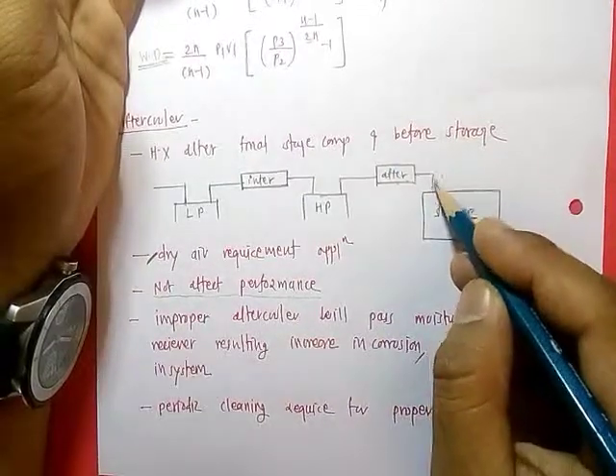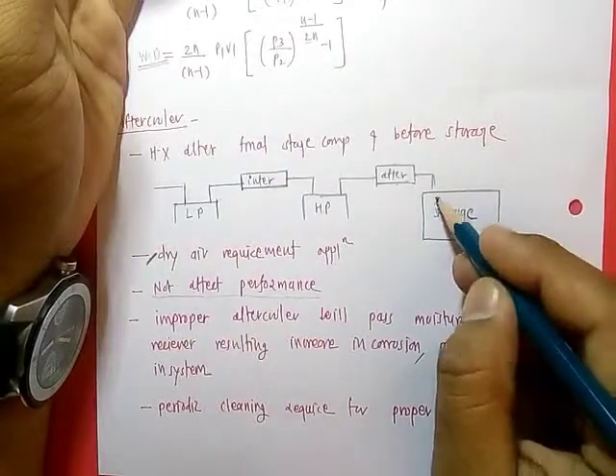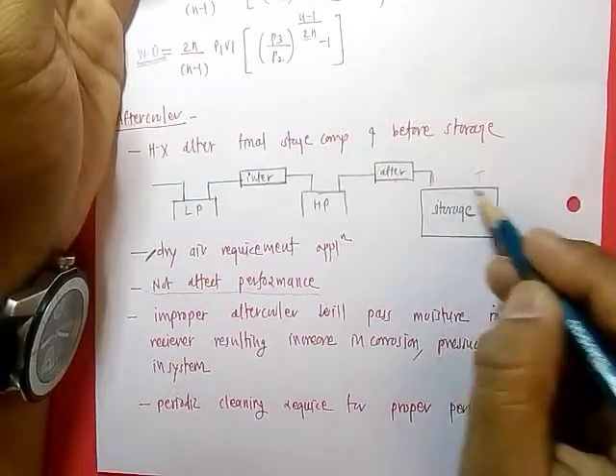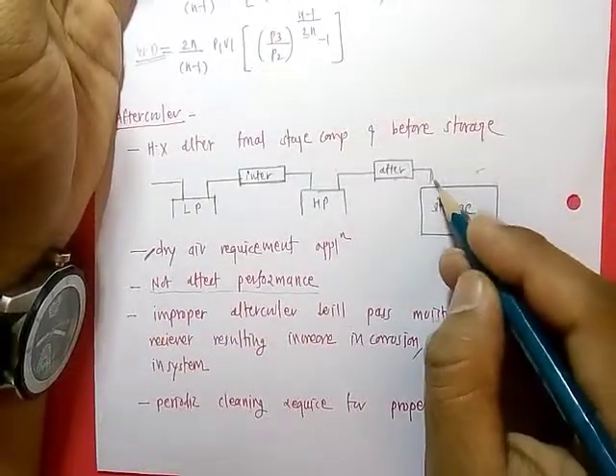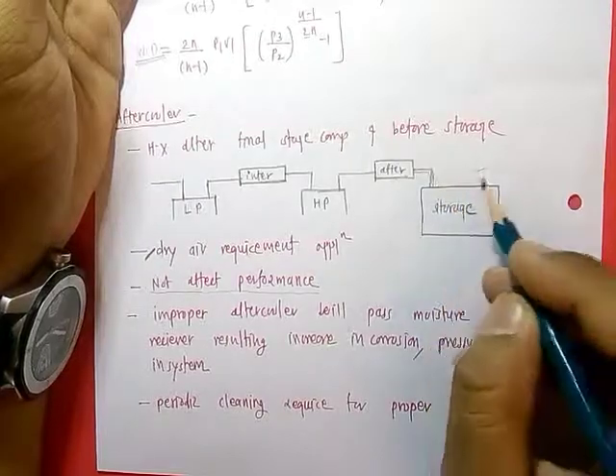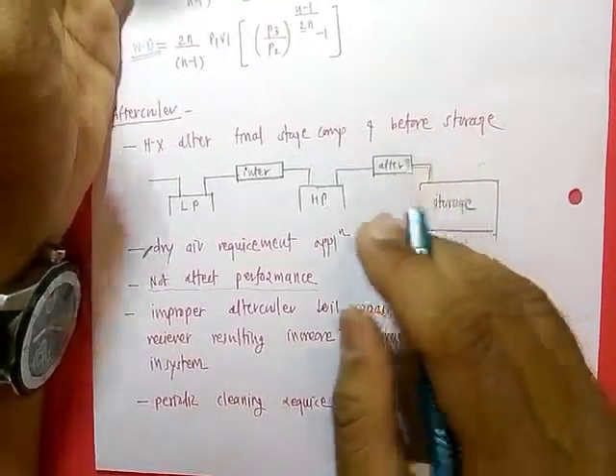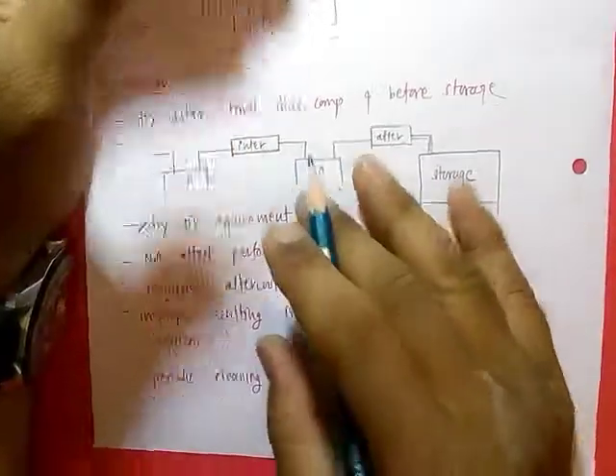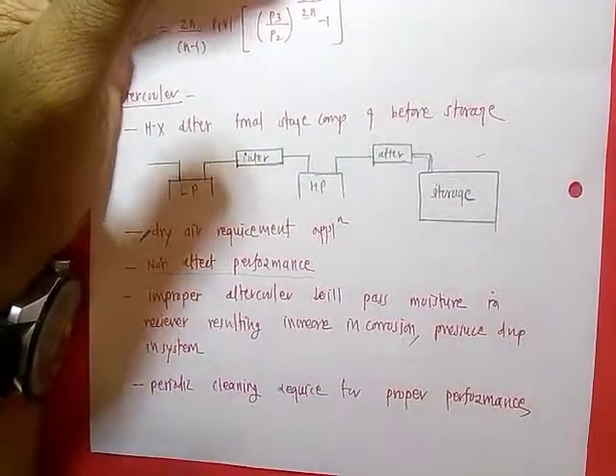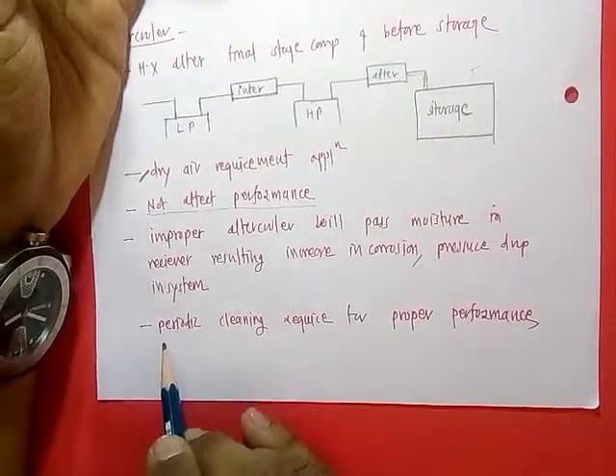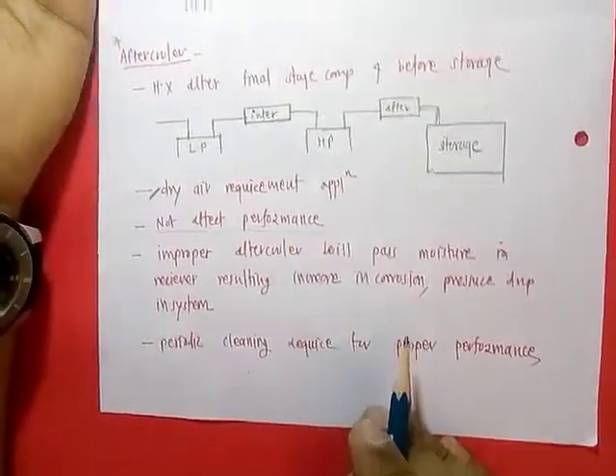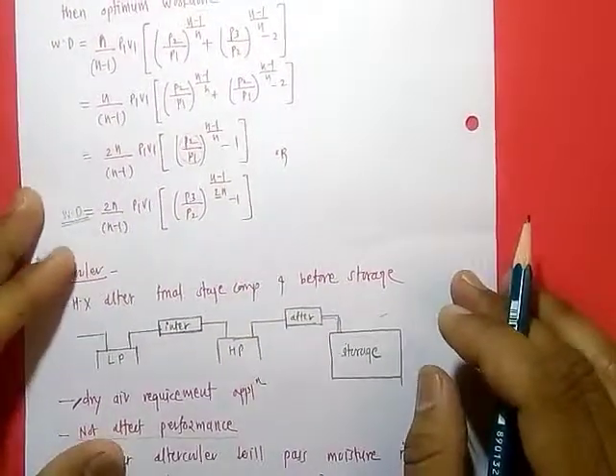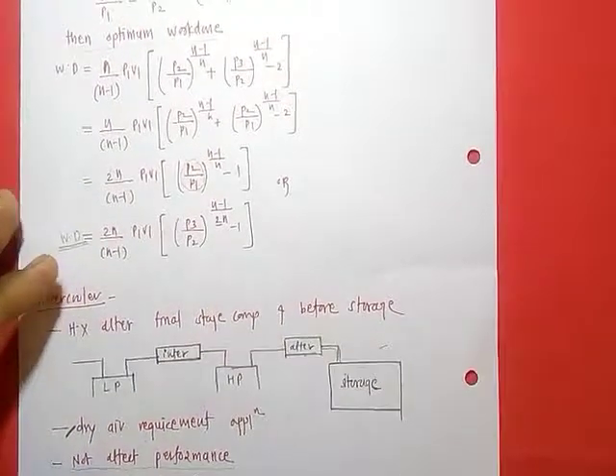If the after cooler is not working properly, there are chances of moist air entering the storage tank. As temperature decreases, this moist air forms water droplets inside the storage tank or in the delivery pipeline. This is responsible for corrosion of the pipe and tank, and it also causes pressure drop because it provides resistance to compressed air flow. Therefore, periodic cleaning is required for proper performance.